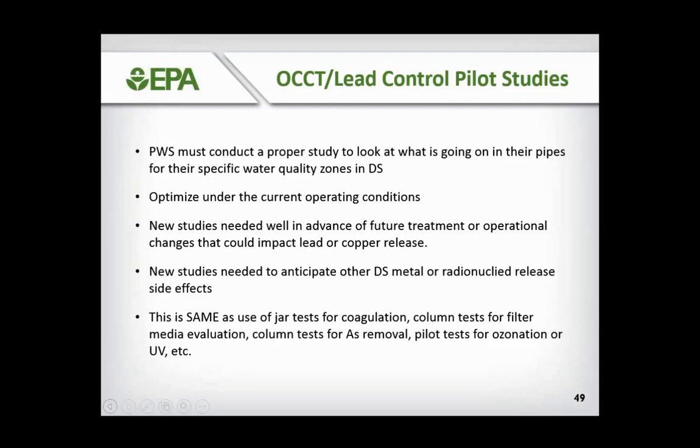And you need to anticipate other distribution system metal or radionuclide release side effects. So this is really the same principle as using jar tests for coagulation or column tests for filter media evaluation. There's nothing really different in principle.